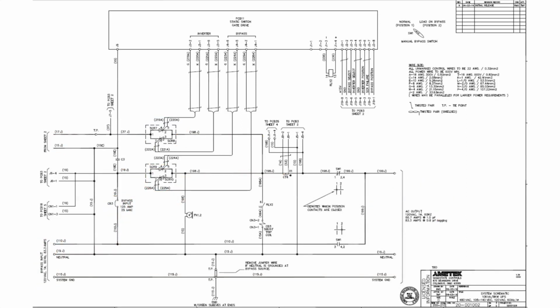Now, to transfer the static switch, there are many circumstances where it is done automatically. We are always sensing the input to the inverter static switch, and if the UPS feels that it is out of tolerance, has gone completely, or if the inverter has failed, there are many situations where the system will automatically say, okay, the inverter static switch input power is not good, so it will immediately switch over to our bypass supply automatically, seamlessly, without a break in the sine wave going out here.